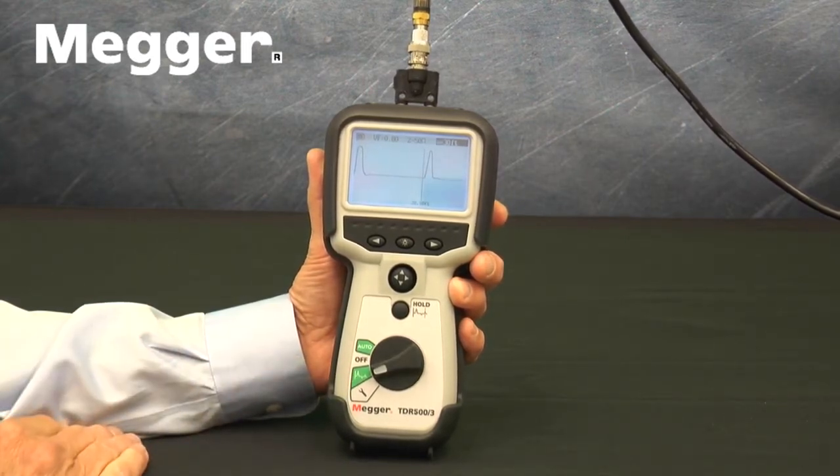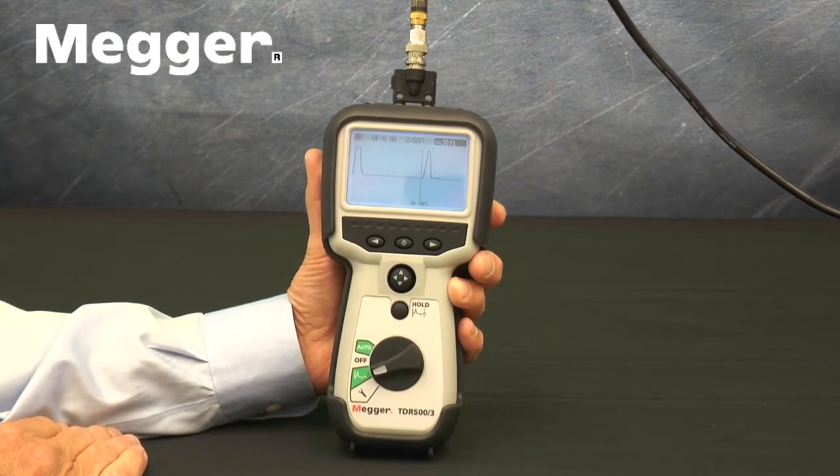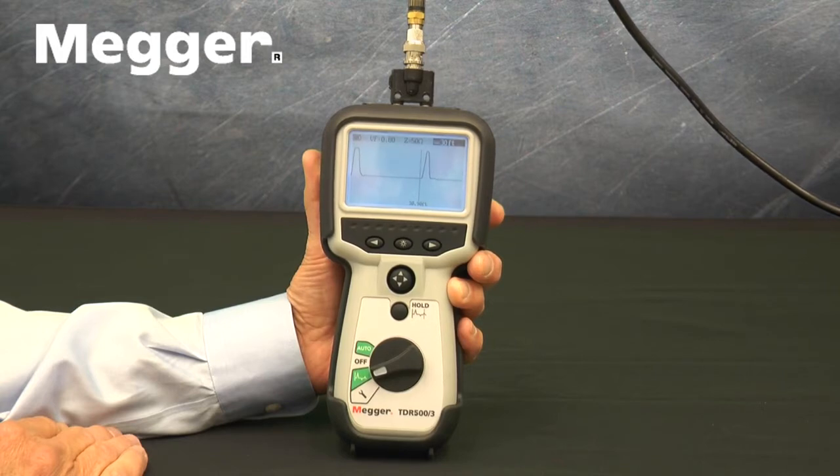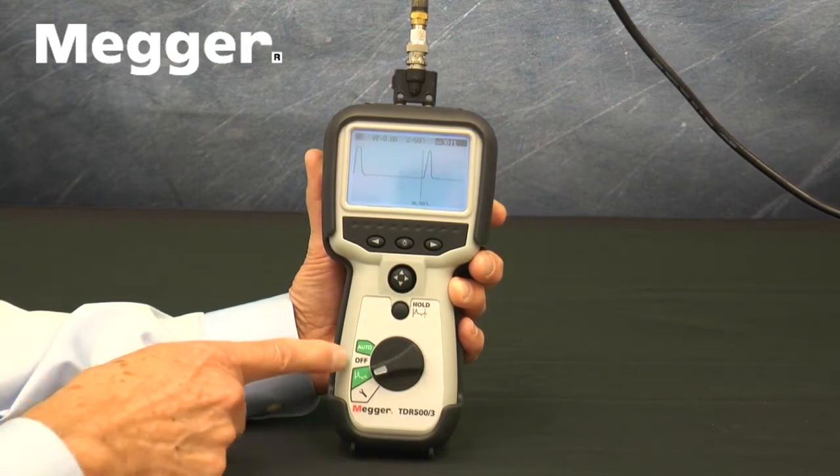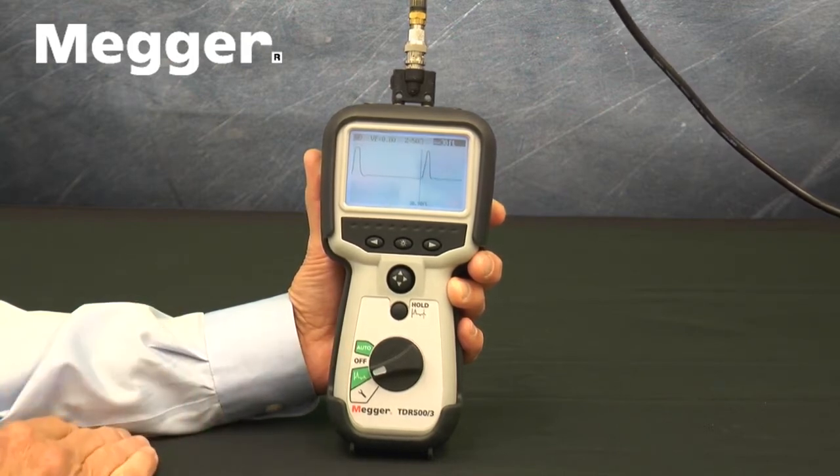This is very much like auto operation, except that in manual operation the user must select the impedance and may override the pulse width and gain settings that the TDR500 has selected as optimal, which it does, even in manual mode. The off setting turns the TDR500 off. It will, however, turn itself off after 5 minutes of inactivity and announces this with a beep.